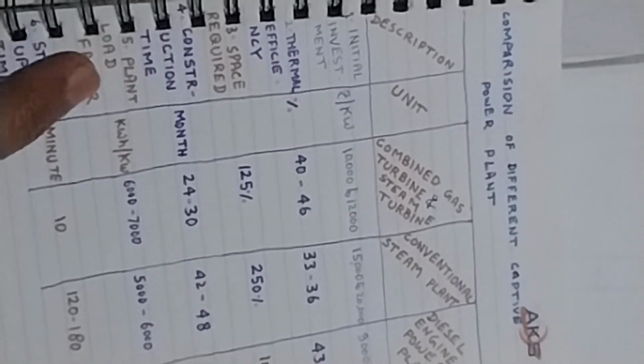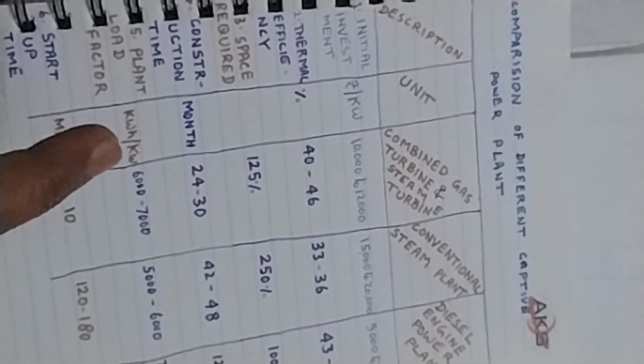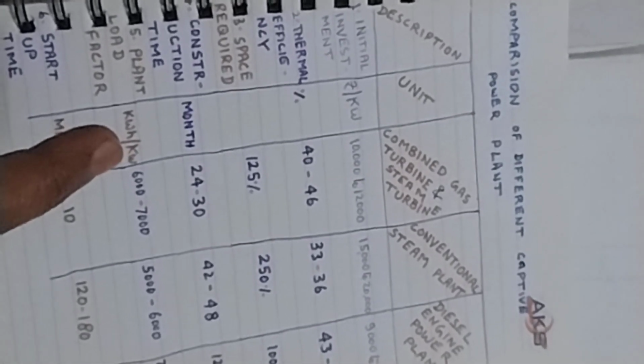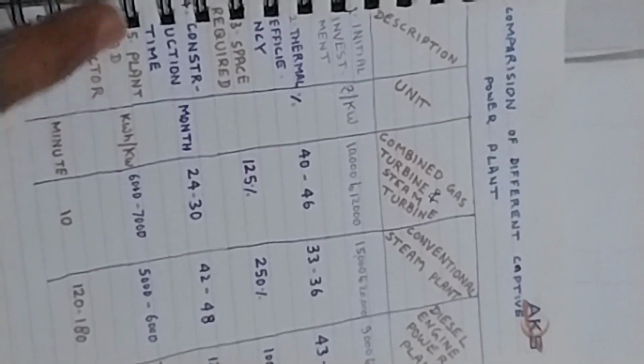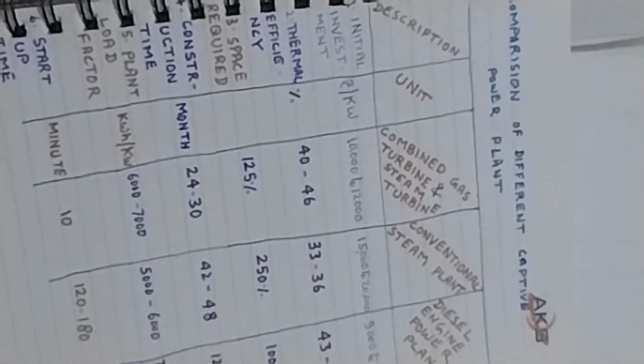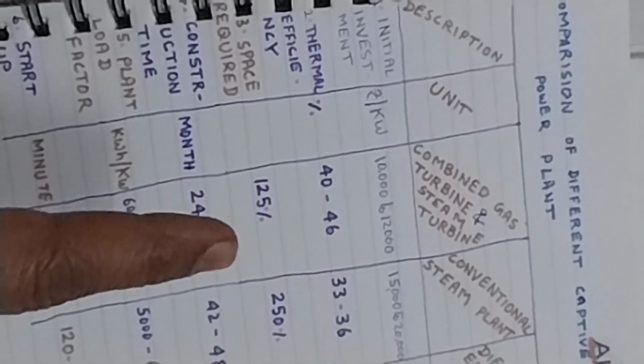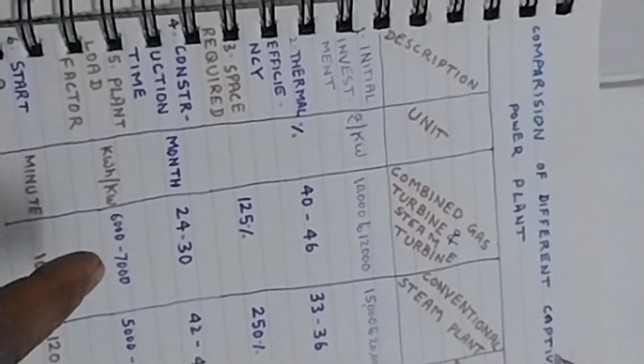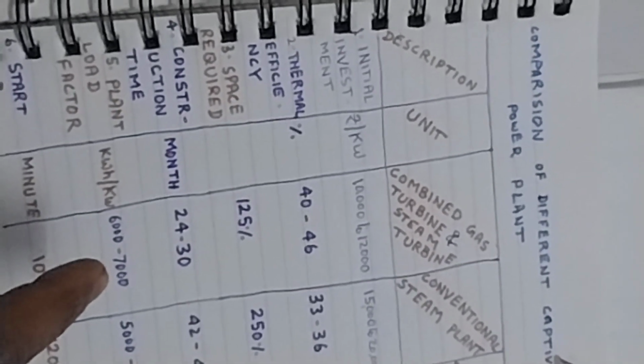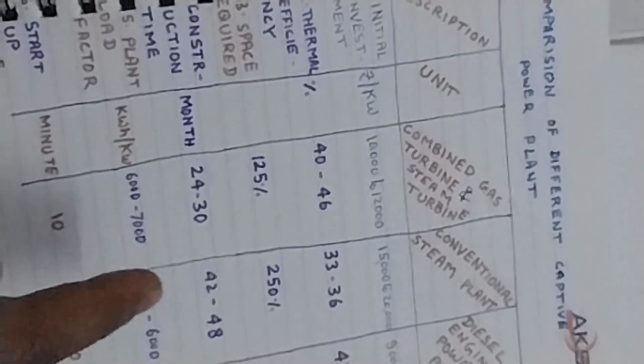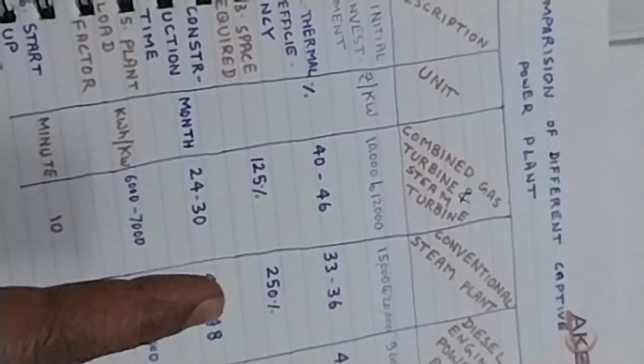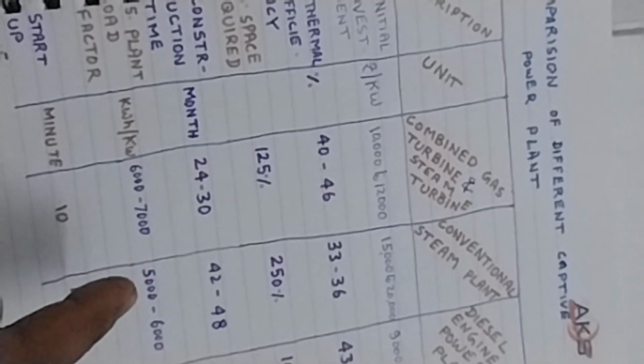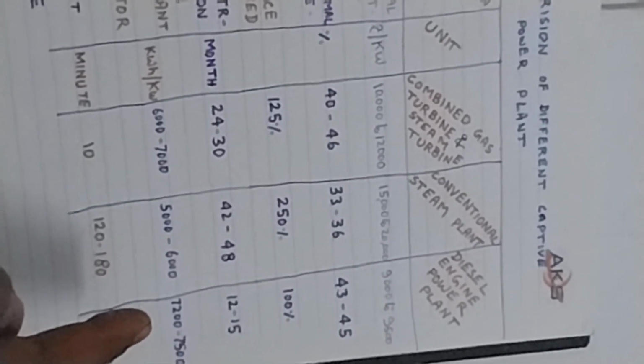Plant load factor, in kWh per kilowatt per year. This is plant load factor per year. It is 6,000 to 7,000 units for combined gas turbine and steam turbine. Maximum is 8,760 units per year per kilowatt. For conventional steam plant it is 5,000 to 6,000 units, and for diesel engine power plant it is 7,200 to 7,500 kilowatt hours.